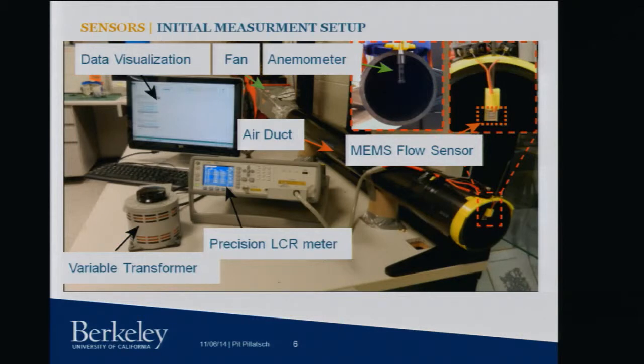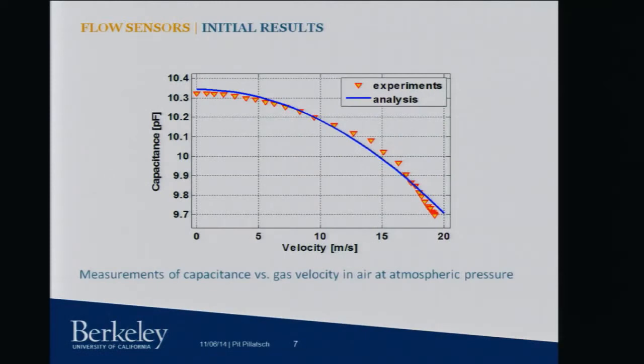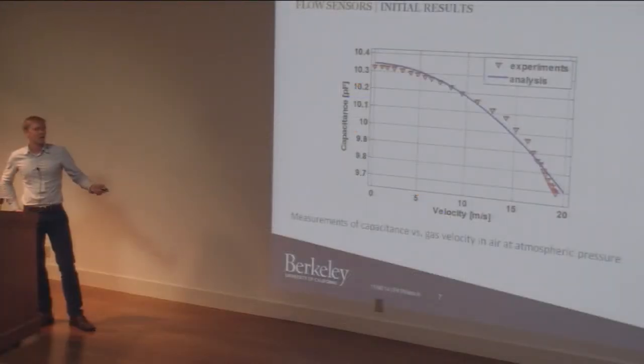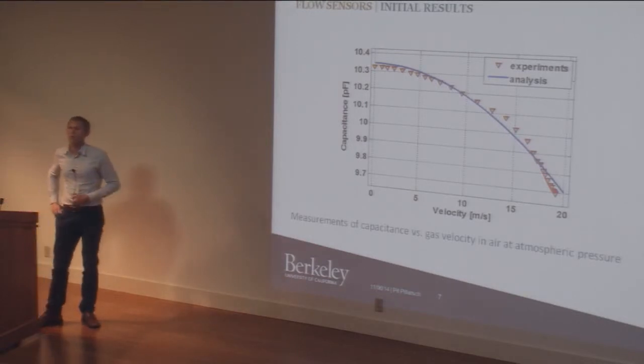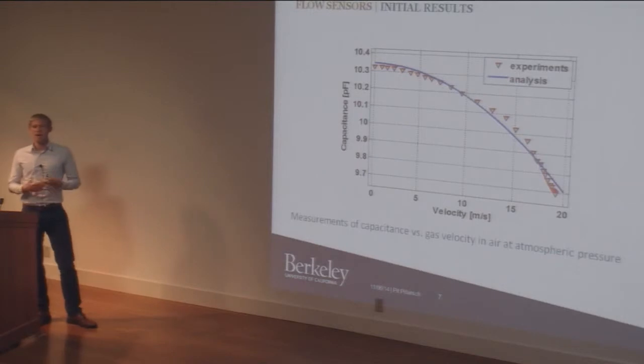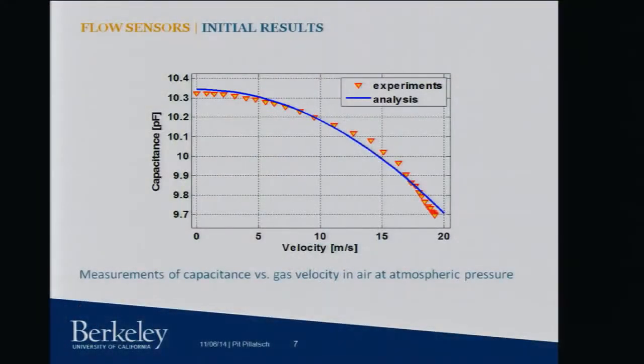With the variable transformer, we can vary the fan speed to see what the sensor does. These are some of the initial results. The blue line is the predicted behavior based on simulation, and the red and yellow triangles are the actual measurement results. You can see the correlation is very, very good. We're achieving very good results, but only in a lab setup that is at atmospheric pressure.